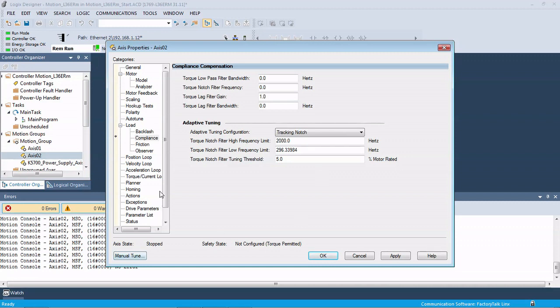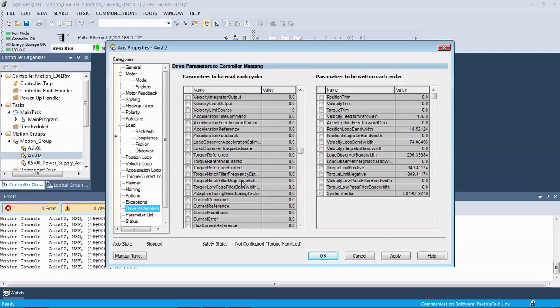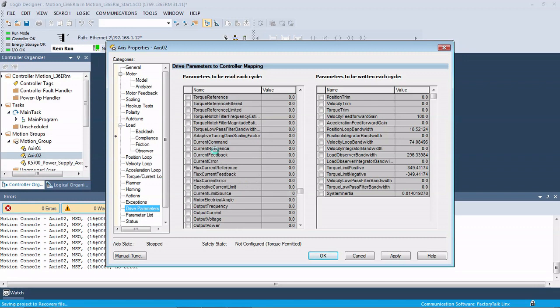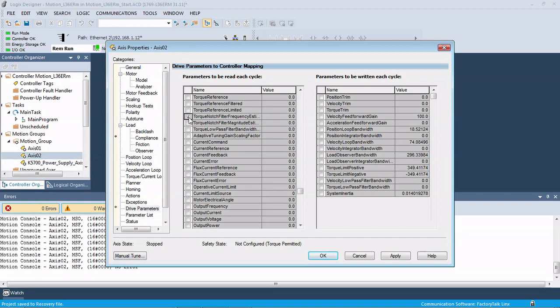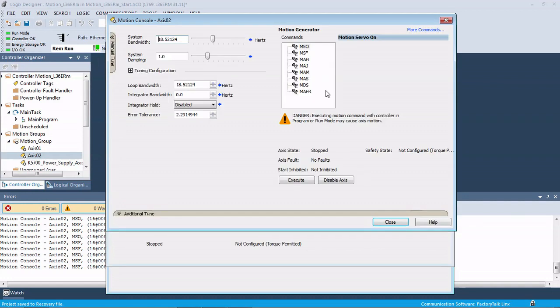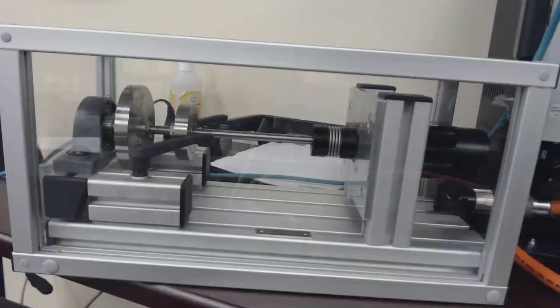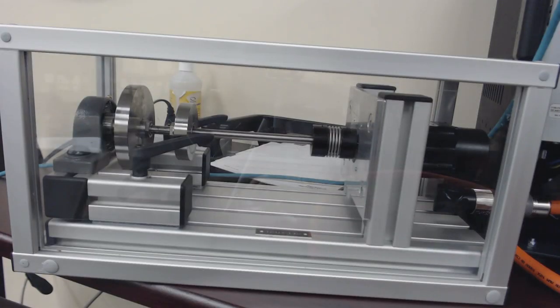So under Compliance, that's where our notch filter is normally set up. We're just going to do this adaptive tuning and turn on our tracking notch filter. Then down here under the Drive parameters, we need to find the Torque Notch Filter Frequency Estimate. We need to check that box and the Magnitude Estimate. These two parameters will be scanned each cycle for the drive. We're going to hit Apply on that and bring up our manual tune and select our motion servo on.